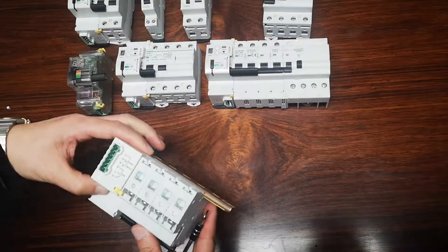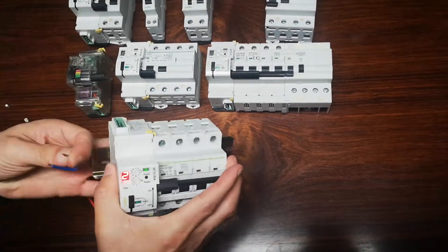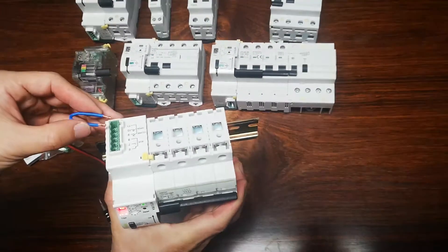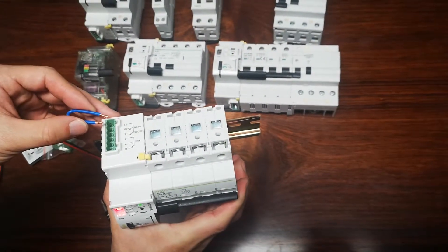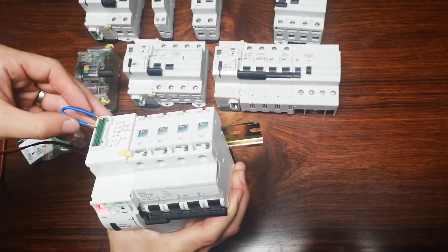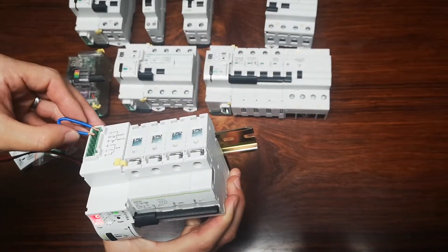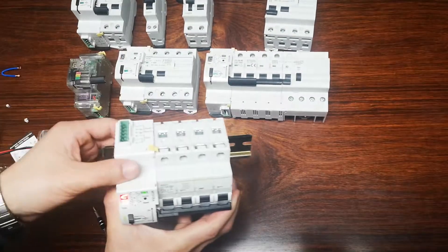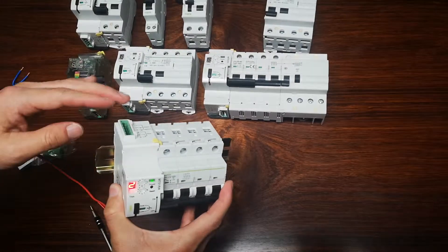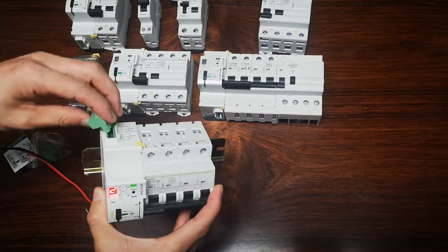With the RS485 module, this is for remote switching on and off. Let's try it: currently it is switched on. For switch off, connect terminals 10 and 11 — now it is open. For switch on, connect terminals 9 to 11. This is showing a direct connection just to demonstrate how it functions. In a real installation you would use proper cables plugged into the terminals.